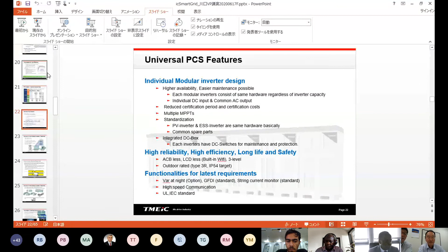Okay, you showed the efficiency of the converters, right? And if I look at the power ratio, the load in percentage, I think 100% is the rated value of the load. Yes. And why do you have the maximum efficiency near 40% and not at 100%?